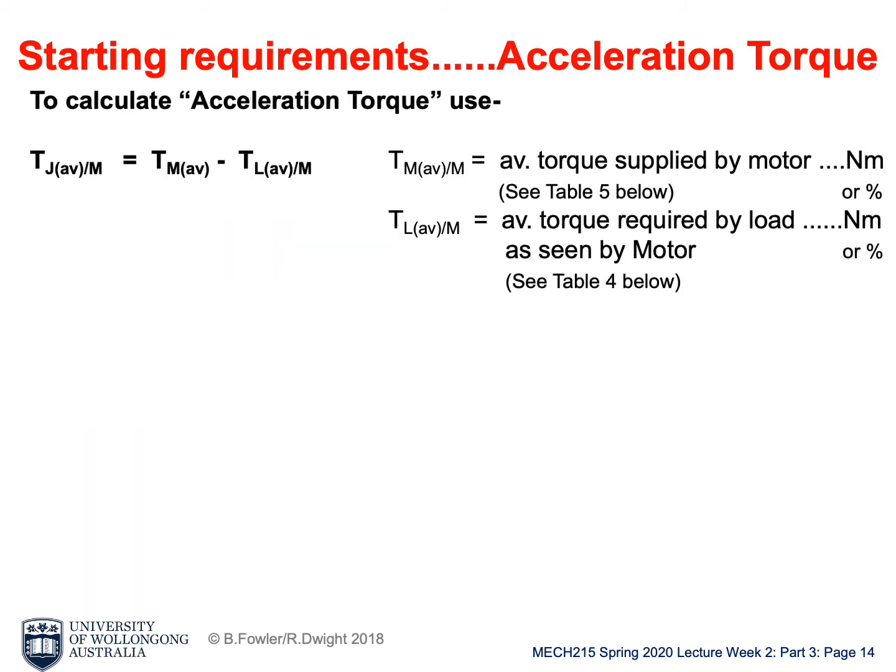With the moment of inertia, if we want to calculate how long it takes to accelerate, we need to calculate the torque first. So torque has three components. The first component is Tm. We have this symbol as Tmav over m, which is namely the average motor torque from the motor side. So that's the motor torque generated from the motor.